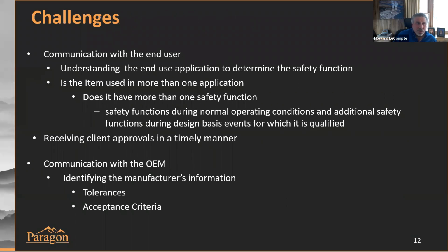So a challenge: communication with end users. We have to understand the end use application and the safety functions in order to determine the failure modes and critical characteristics. Is there more than one application? I know a lot of engineers, when they do the technical evaluation at the utilities, include all the applications, so we need to know how many applications there are. Is there more than one safety function to consider? Do we need to look at not only normal conditions, but any design basis safety functions throughout the dedication process?